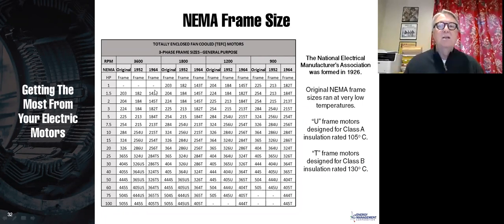Then in 1964, they came out with a T-frame motor. A T-frame motor is much closer designed. You'll notice that every time we redesigned this, we were able to get the same amount of horsepower in a smaller frame size, meaning a smaller motor. The T-frames are still what is in effect today. And so if you have, let's say, a 254 T-frame, then you should be able to replace that with a 254 T-frame from any other manufacturer.